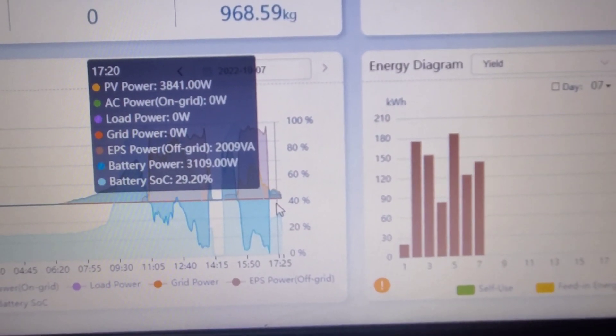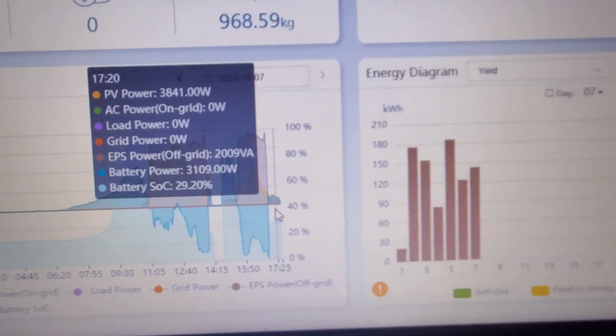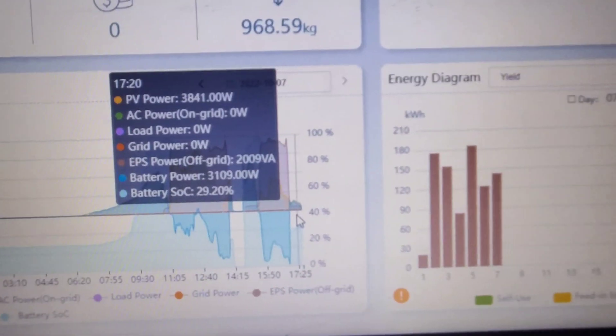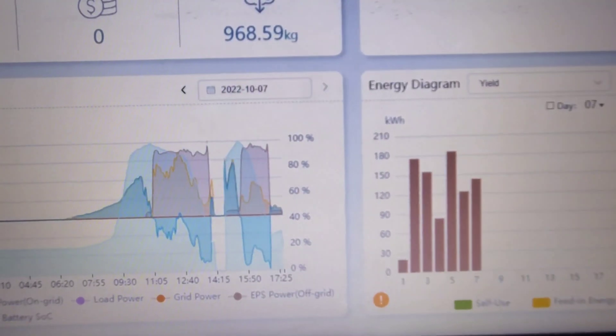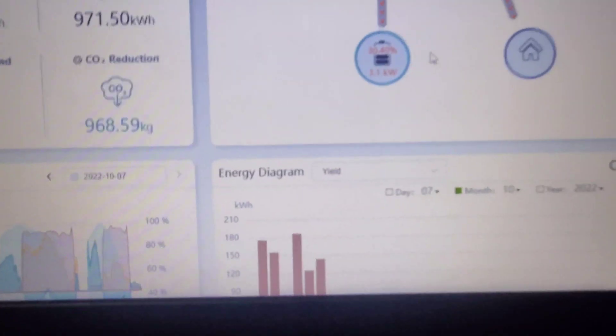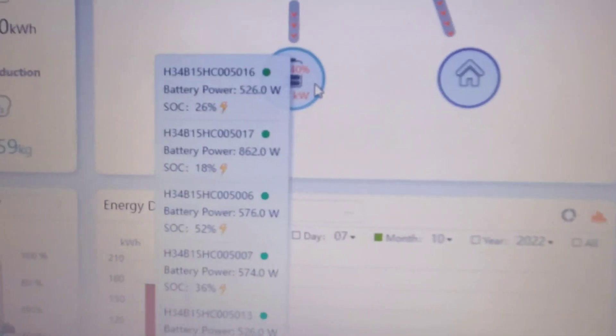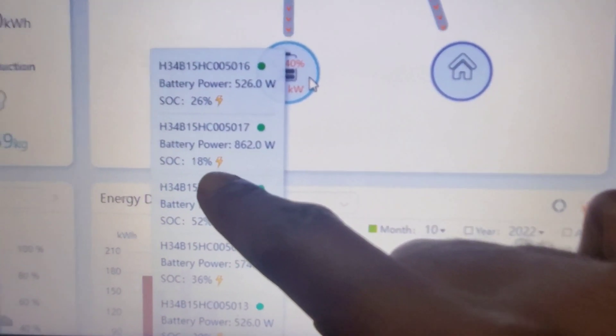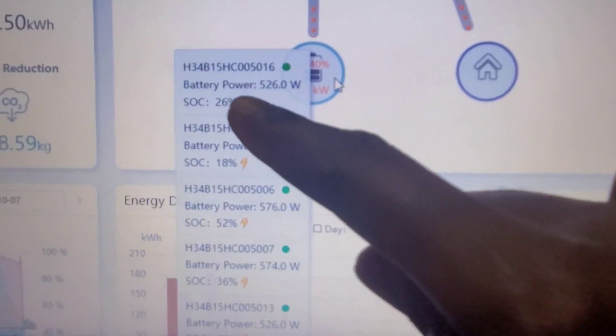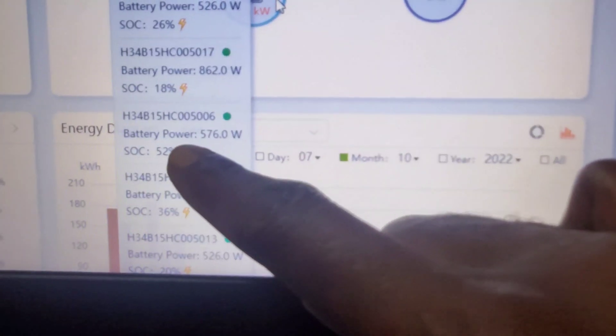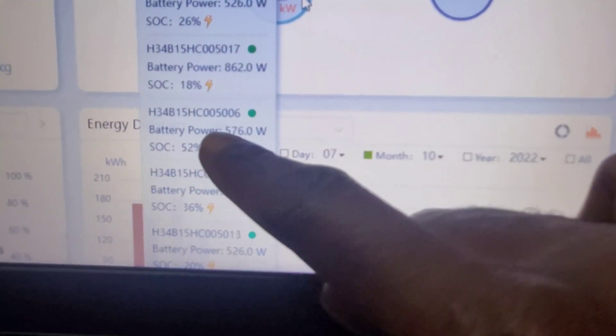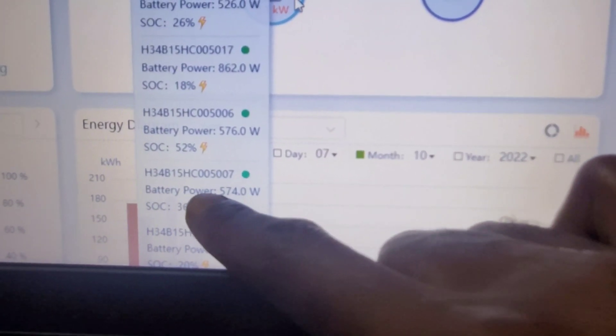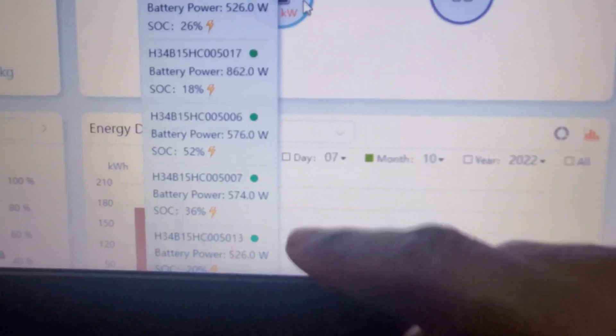We turned it off again because we started to drop inverters because we had hit the low percentages. Remember I was showing percentages on the batteries—you can see there are differences. This one is at 18%, this is 18%, this has 26%, this has 52%, this has 36%, and this one down here is at 20%.